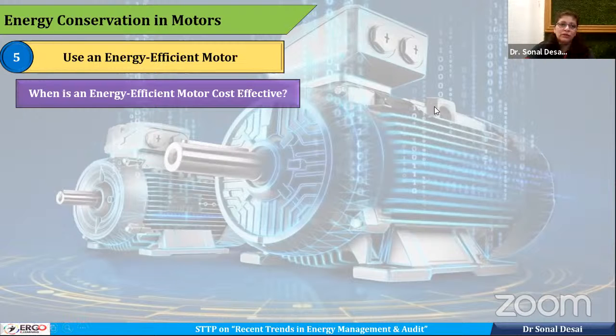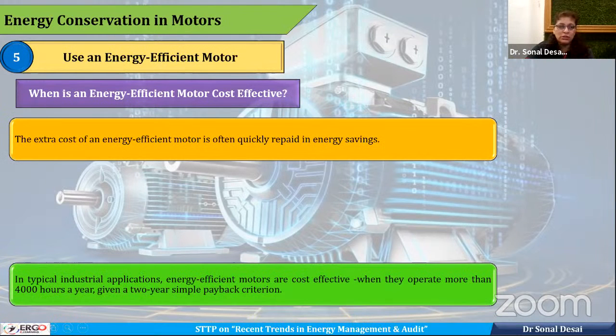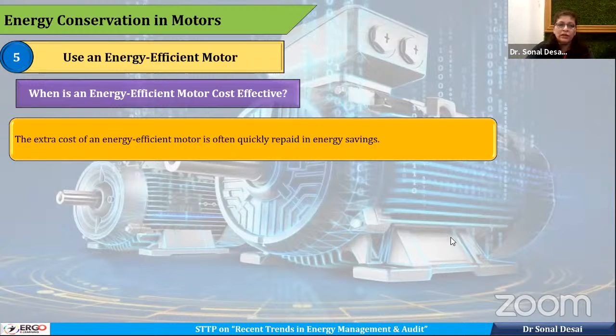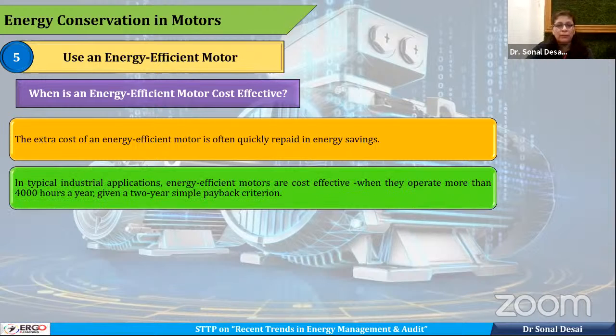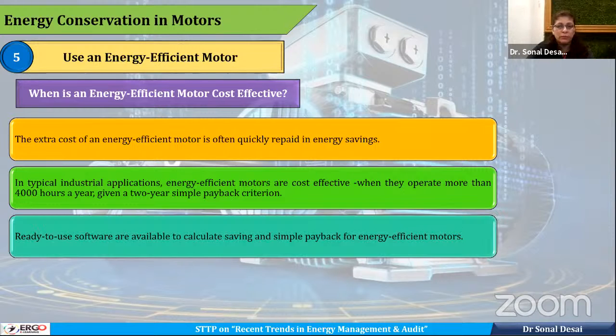Here, the fact is shown of when an energy efficient motor is cost effective. When the extra cost of the energy efficient motor is quickly repaid in terms of payback, then it is good. When we operate it for more than 4,000 hours per year, then it is good. It will have a payback of less than 2 years, which is always recommended.